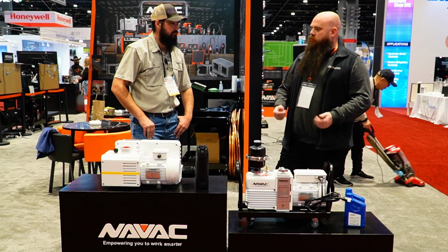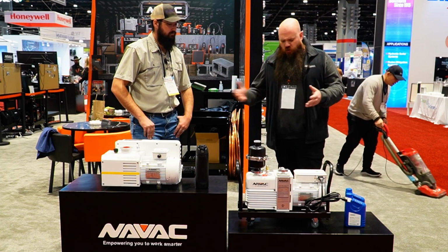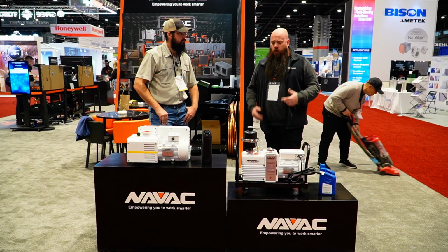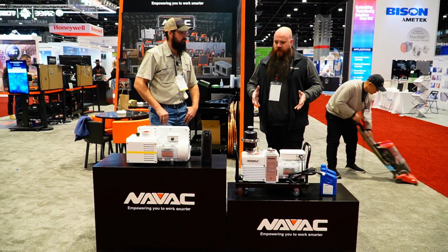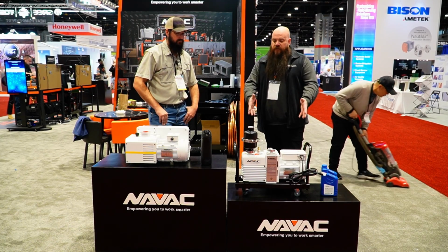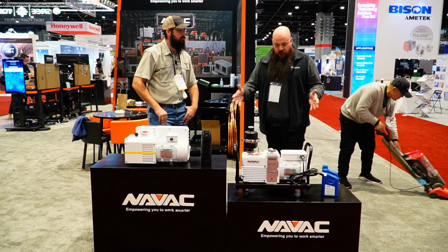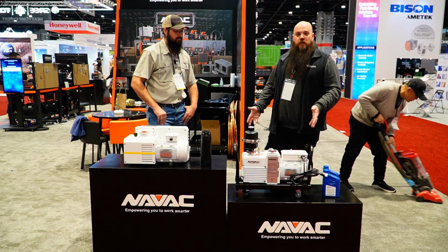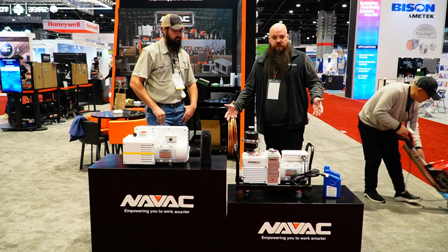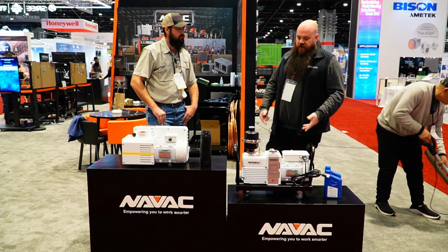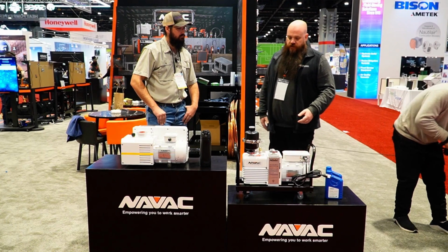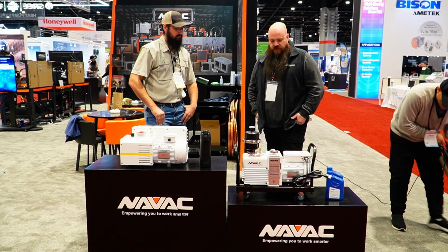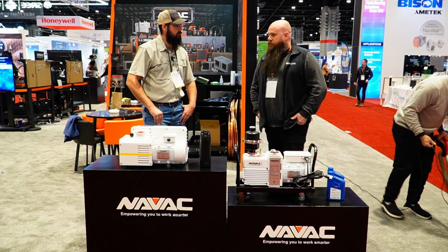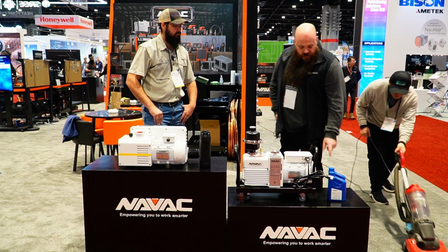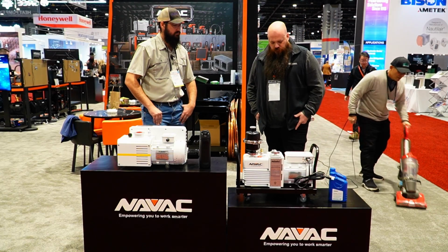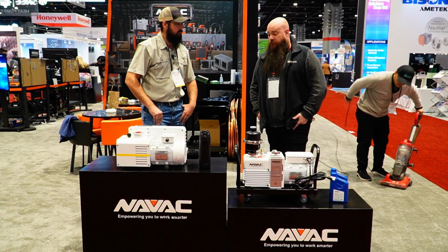So can you throw typical mineral oil in it? Sure, typical vacuum pump oil, but you may not get quite that thermal performance that we expect to see from a really heavy machine for the CFM. So this monster here is 90 plus pounds, it's 12 CFM, and one might think this should be a much higher CFM, but a large element to this is that it's designed as a large heat sink. That, coupled with the formulation of this oil, is what enables it to perform as advertised.